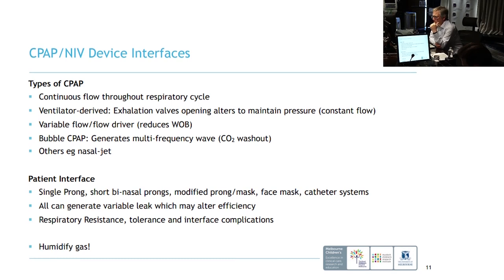I think what's more important is the patient interface. They're all designed to have a leak - that's critical. Unlike high flow, that leak is probably more important. With high flow you want a very, very large leak. On CPAP you generally want a smaller leak, but then you come at the problem of potentially getting skin contact issues. You have different systems.